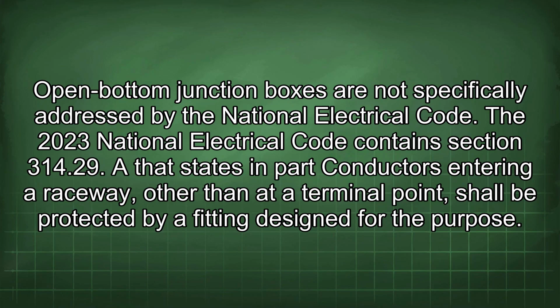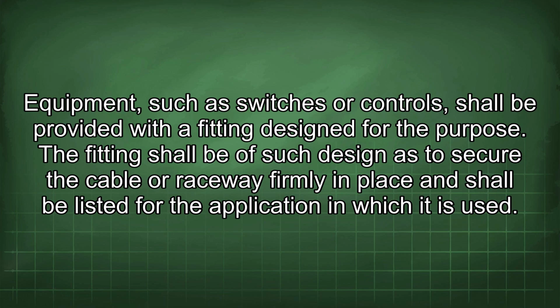Open bottom junction boxes are not specifically addressed by the National Electrical Code. The 2023 National Electrical Code contains Section 314.29. That states in part: conductors entering a raceway other than at a terminal point shall be protected by a fitting designed for the purpose. Equipment, such as switches or controls, shall be provided with a fitting designed for the purpose. The fitting shall be of such design as to secure the cable or raceway firmly in place and shall be listed for the application in which it is used.